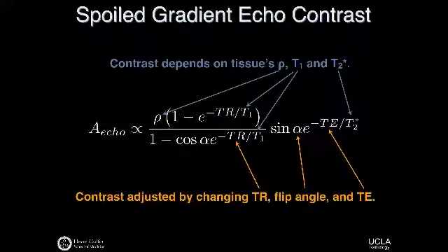And then the other thing that we control here now is the flip angle. We didn't have this in the spin echo sequence. The spin echo sequence was defined for us. It was a 90 and a 180. And in the simplest case, it's always a 90 and a 180. In the gradient echo sequence, we can control the flip angle. The flip angle is the excitation flip angle. So when I have spins at equilibrium, I could tip them with a 90, and I'd have a 90-degree flip angle. But there's also reasons that you might only tip them by 10 degrees and let them relax. And the main reason you do that, if you tip by 10 degrees, they get back up more quickly, right? And so that actually helps with fast imaging as well. But changing the flip angle will change our contrast, and I'll give you some insight about that in just a second as well.